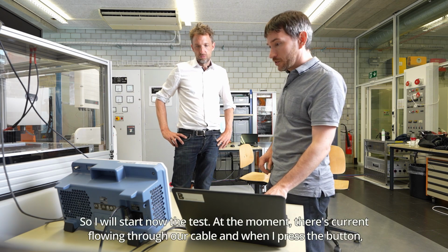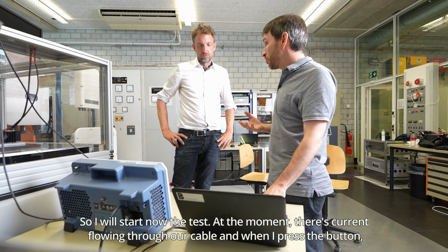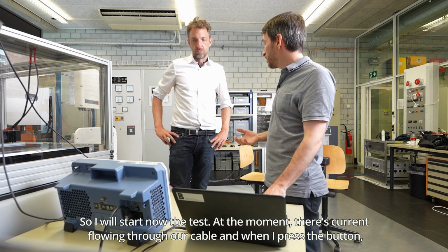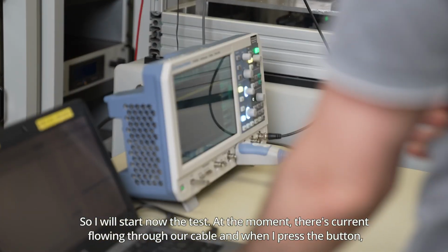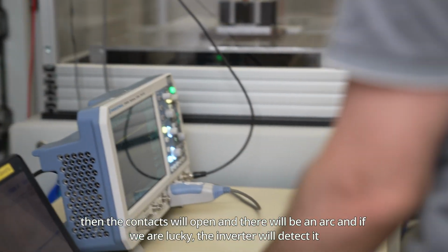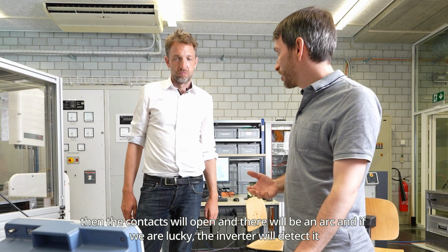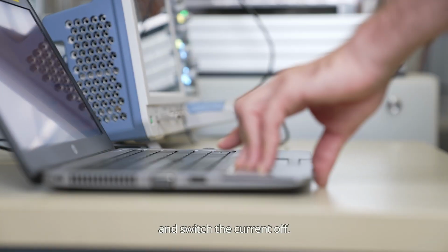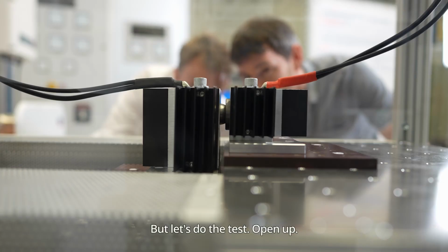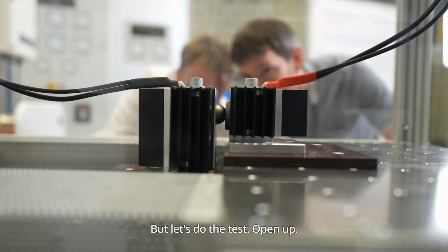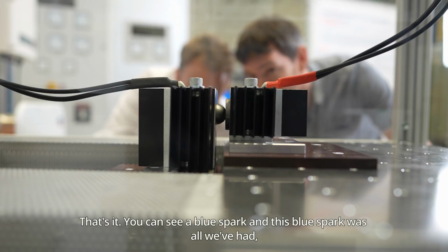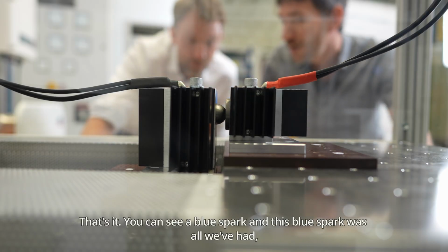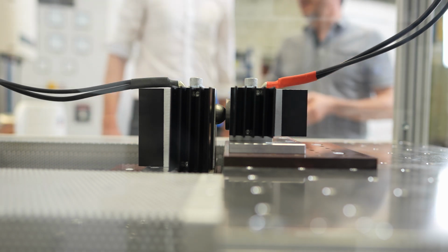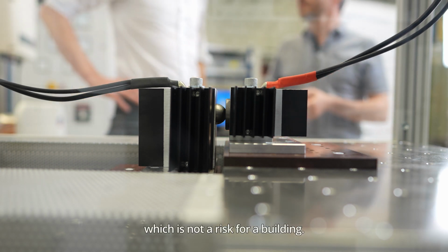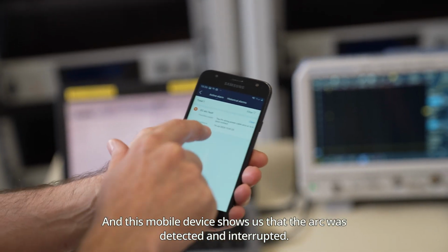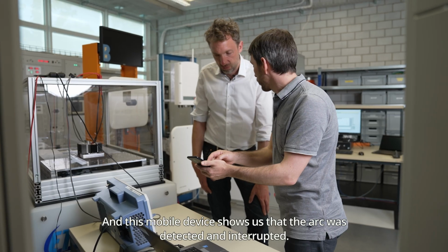So I will start now the test. At the moment, there's current flowing through our cable. And when I press the button, the contacts will open and there will be an arc. And if we are lucky, the inverter will detect it and switch the current off. But let's do the test. That's it. You could see a blue spark. And this blue spark was all we had, which is not a risk for a building. And this mobile device shows us that the arc was detected and interrupted.